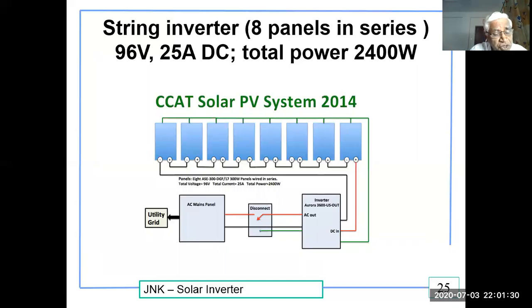Now, the string inverter topology is more resilient to mismatch than the central inverter, because each string is independently operated at its MPP, thus guaranteeing a higher energy yield. String inverters are smaller than central inverters. However, the implementation is more complex than the module inverter. Also, partial shading will have a greater influence on the string inverter topology than on the micro inverter.